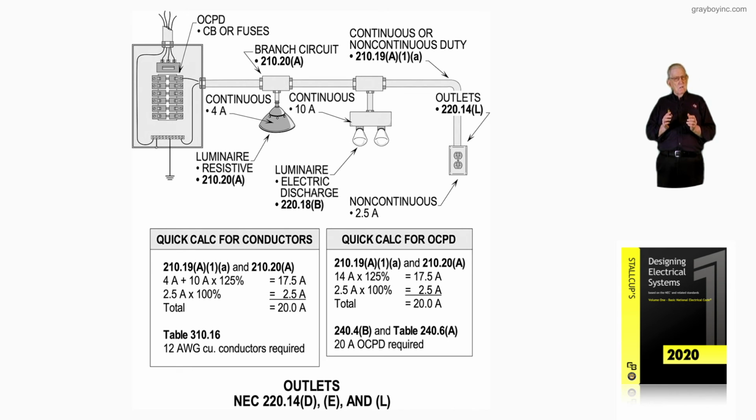So what does this tell us as designers, electricians, inspectors, maintainers, whatever? That the 125% application derates the breaker to 80% loading for continuous duty. 100% of the load would be taken if the loads operate less than 3 hours. And that's what our Figure 14-21 is illustrating, along with the conductor.